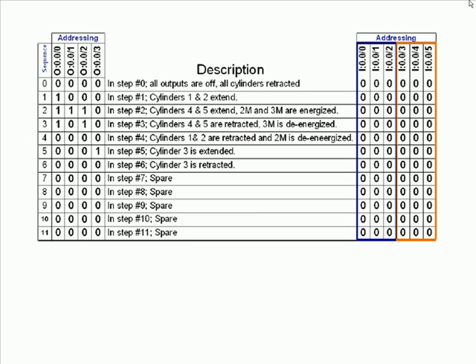Now what we had you do in this step is: for step zero, with all the outputs off, what state should the inputs be in as a result of all the outputs being off? So you look at step zero, you see all the outputs are off, you go back to your diagram for the process in your manual. If all the outputs are off, all the cylinders are retracted and we'll say there's more or less no product on the conveyor. Then you go in and put in one if the sensor would be on, zero if it would be off. One little nuance here: in order to go to step one we need to show product presence, so keep that in mind.